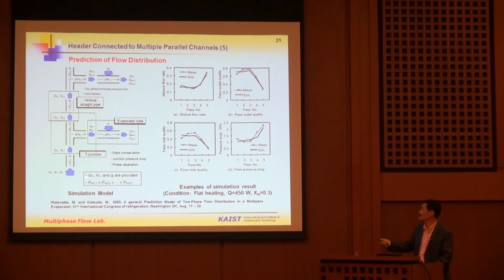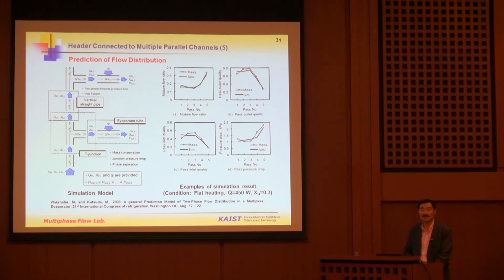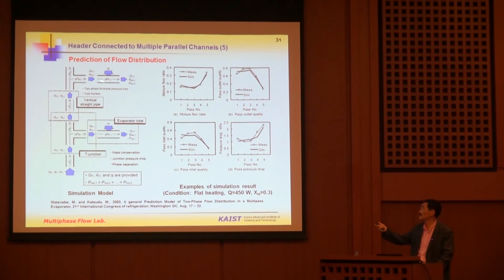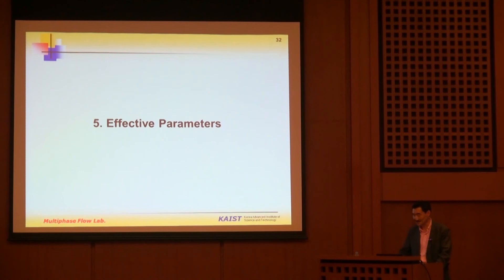Work by Watanabe shows that by modeling the T-junction, the pressure drop in the evaporator tube, and the straight pipe together, you can obtain the flow rate split to the branch quite reasonably. However, near the end plate, the pressure drop along the channel is usually quite large, so the role of the last junction is somewhat underestimated — which is why the model appears to fit well there.